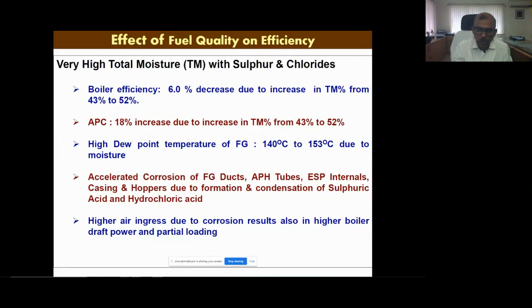In auxiliary power consumption, the other major factor, apart from technological issues like the large number of rotating drives and milling plant, this increase in moisture itself is causing around an 18% increase. That is in the boiler component. And because of this moisture increase, the dew point of the flue gas is also increasing from 140 to 150, which is detrimental, causing corrosion and other problems. This results in accelerated corrosion in the FG duct, APH tube, ESP internals and hoppers, and creates condensation of sulfuric acid and hydrochloric acid. Higher air ingress due to corrosion results in higher boiler draft power, because of air ingress through the casings and the flue gas ducts, leading to derated loading and resulting in lower load and partial loading.